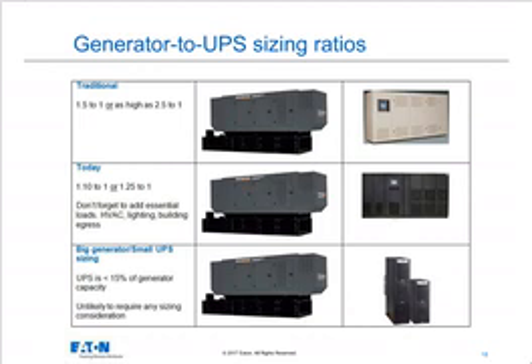Now, suppose you have an application where I have a large building like a hospital or a large data center, for example, and I have a humongous generator out in the backyard, and I'm dealing with a relatively small UPS, where the UPS is maybe less than 15% of the size of the generator. In those cases, we almost always find it unnecessary to do any kind of sizing there. The disparity in size, the UPS is so much smaller than the capacity of the generator that it doesn't cause a problem. So in the case where you have a very large generator, very small UPS, it is unlikely you'll need to pay much attention to sizing in that case.